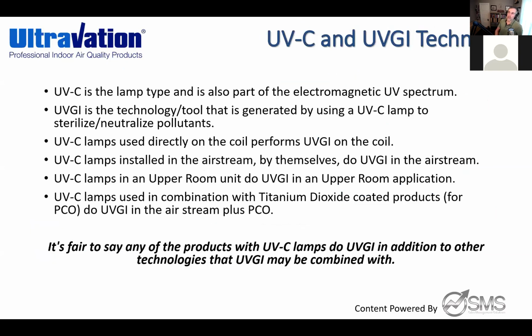After the review of UVC, this is the point we like to really dig in. If we're speaking on ASHRAE guidelines for the HVAC industry, this is the same training I run contractors through, so they're more informed. Just reminding people, UVC is the lamp type, that specific dangerous form of the electromagnetic spectrum. If you're applying products using UVC into an HVAC system, then technically you're using UVGI technology. So if I'm applying UVC lamp products to a coil, I'm applying UVC for surface area coil performance. If I'm applying UVC products into the supply duct, I'm dealing with airstream.